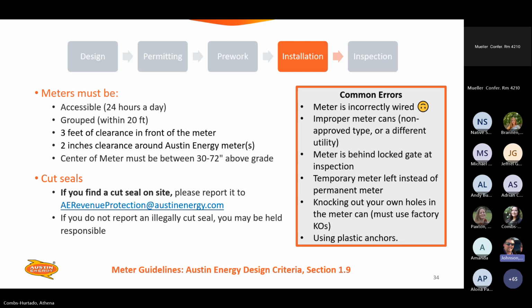Cut seals. If you find a cut seal and you didn't do it, immediately report it to AE Revenue Protection at austinenergy.com. If you do not report a seal and we show up for an inspection and you're there, we only have what we're faced to go off of. You're there, the seal's cut, and we're here to inspect this new system. Don't have much to work with there. At that point, we have to report that we found a cut seal and a minor investigation we performed, and it will either go to the contractor or the home or business owner, whichever one that meter is tied to.